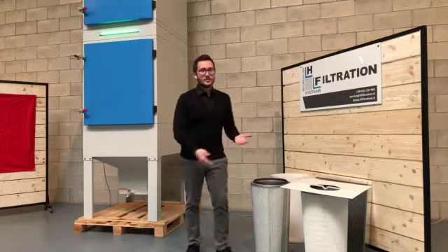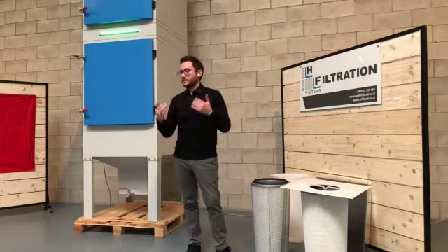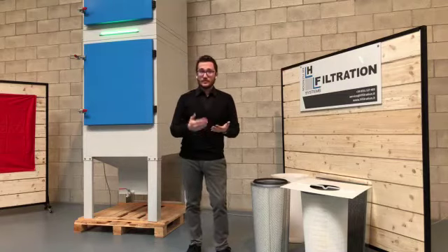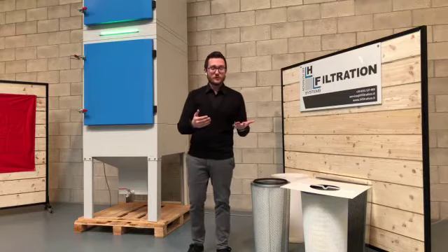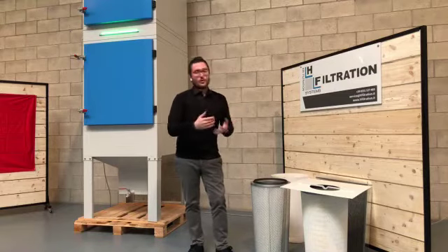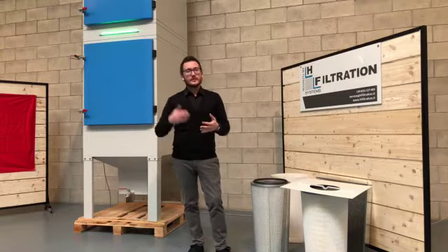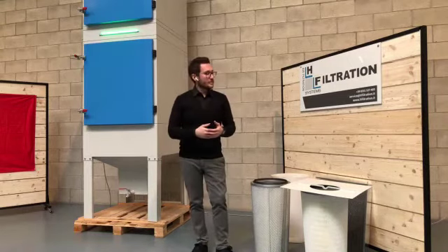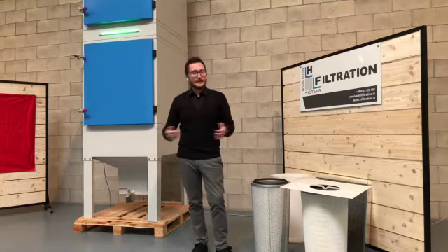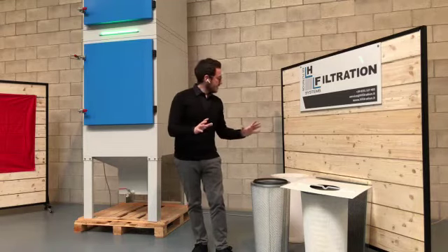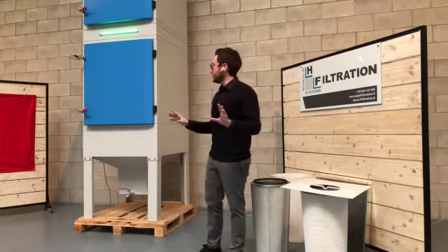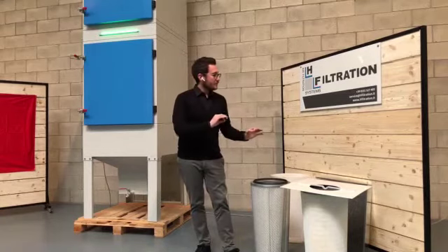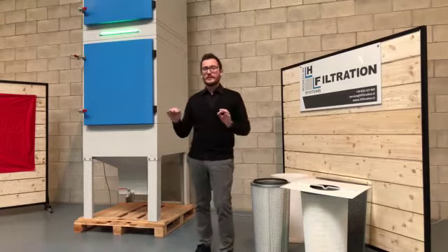Because the cartridge gets clogged, so the filter doesn't work properly. The filter will suffer from that kind of oil smoke, the white smoke. So you should go for another kind of filter which works with the coalescence principle, the MCOS, which is our mist compact oil and smoke. So basically, I think that more or less we have spoken about the components of the filter, and all the things that should be taken care of.